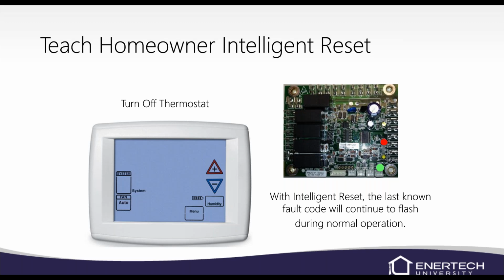It could be that they reset it and it takes off fine. And if it takes off fine and then you come out the next day and there's no lockout on there, it's hard to troubleshoot. So if they reset it at the thermostat, it holds that code. When you get out there, it'll still be there for you. If they reset the unit and it runs fine, those are always the hardest problems to diagnose, when it works fine when you're out there. It happens to me all the time. I get called out to these site visits. They've reset it, I get out there, it's running fine. I check everything. There's not much I can do. So I just tell them, hey, next time it does it, just turn it off at the thermostat, wait 30 seconds to a minute, turn it back on, and we'll go from there.